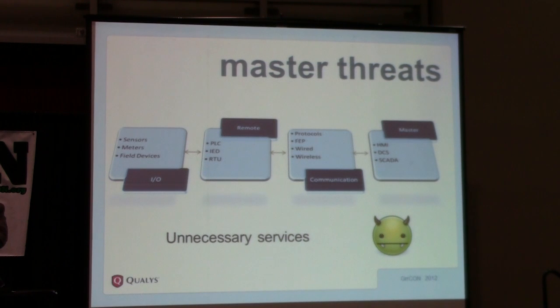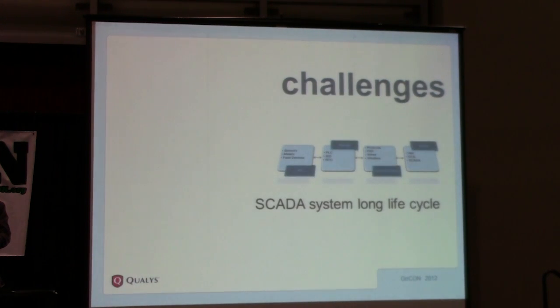Since now, as I mentioned, these are off-the-shelf operating systems, your Windows, Linux, and I don't want to just beat up on Windows, I mean any off-the-shelf operating system, Solaris. There are a lot of unnecessary services running. So now you have to do a lot of security management on this system that you would do on a normal IT system. You have to make sure that this system doesn't have, for example, a mail server running just because it came by default like that. And off-the-shelf software, we talked about this already.